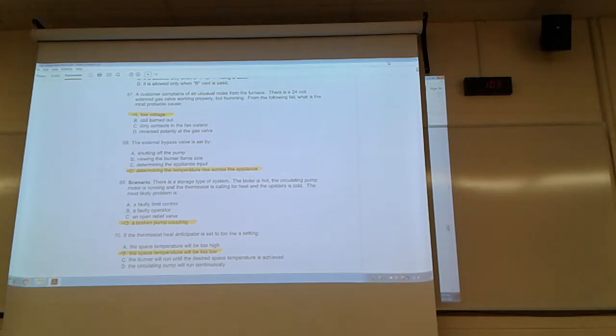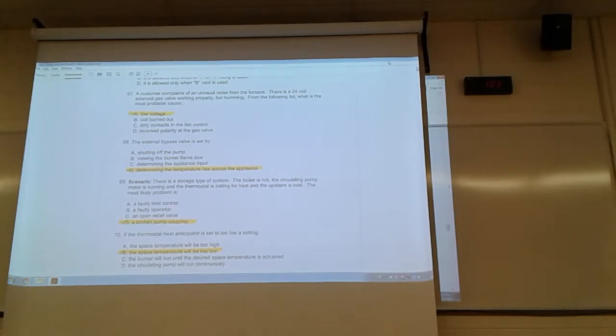68, the external bypass valve on a pool heater is set by determining the temperature rise across the appliance. So even though they don't tell you it's a pool heater, it can be a hot water heater as well. They can have external bypasses as well, and that is used to balance out the temperature rise across an appliance.